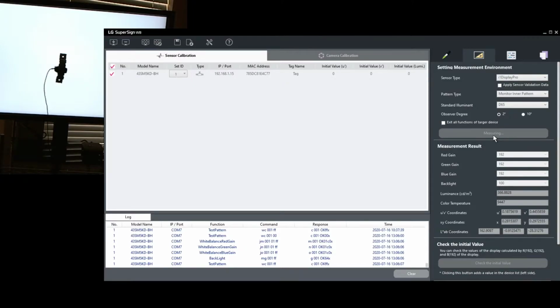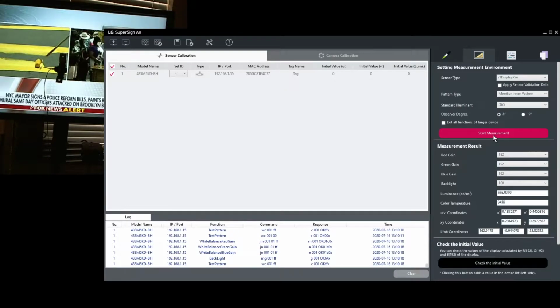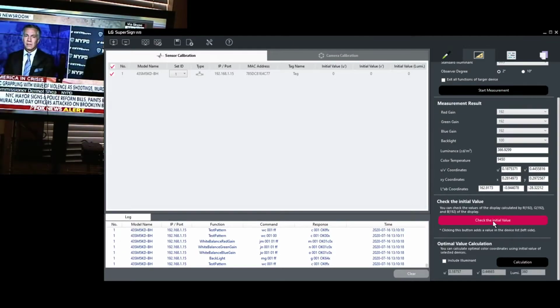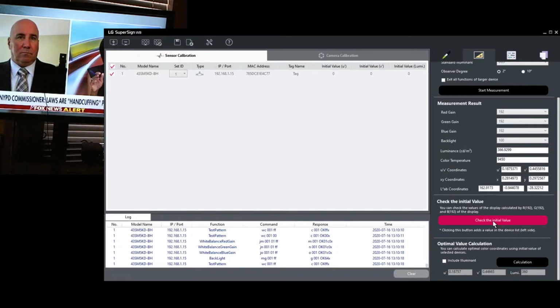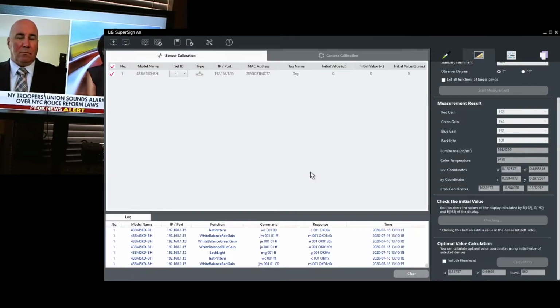As you can see on the left side of the screen, the display went to a white screen, and the software is actually doing a measurement function of the display. So once that measurement is completed, we'll want to step down to check the initial value. Now we can document the measurement results of the display. Sometimes it's easier just to look at it and pay attention to your luminance value and color temperature numbers, 366.9299, and then color temperature at 9450. So we'll do a check the initial value, and then press done to proceed on.